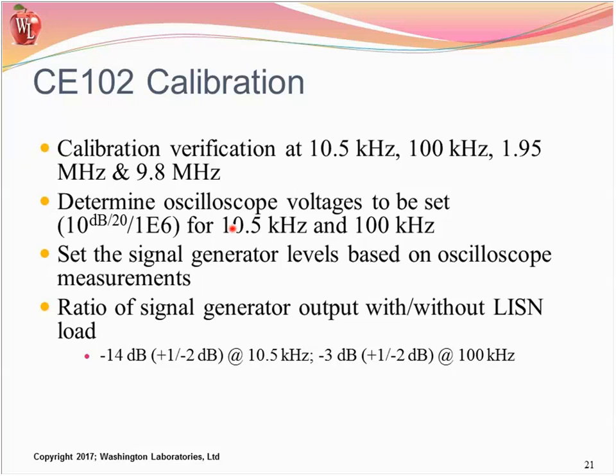Remember that the 10.5 kilohertz to 100 kilohertz range is below the 50 ohm impedance of the standard LISN. So you need to measure the signal, because if you just connect the signal generator, the LISN will load it, and what the signal generator says is not what's really being applied. Set the generator levels based on the oscilloscope.